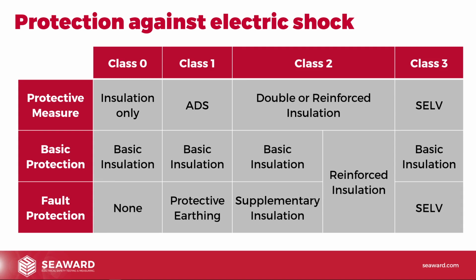So Class 1 equipment, this is the protective measure ADS, automatic disconnection of supply. And the basic protection is provided by basic insulation. If the basic insulation fails, we have protective earthing. Anything that's conductive, that could become live if the basic insulation was to fail, will then be connected to earth. We get automatic disconnection of supply, the current flows to earth, operates the protected devices, disconnects the supply, ADS.